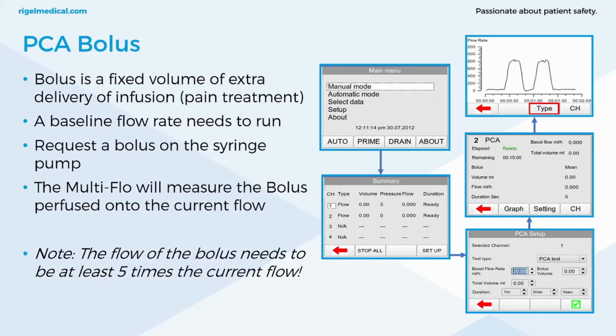We've got bolus, which is a fixed volume of extra delivery to the patient. Pain treatment, so the patient typically delivers this self-medicated. A baseline flow rate needs to run. So we've got this baseline flow here, and then we've got these boluses which are being administered. The Multi-Flo will measure these boluses perfused onto the baseline current flow.